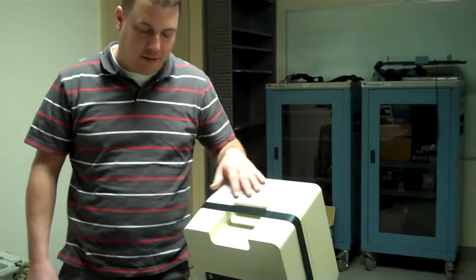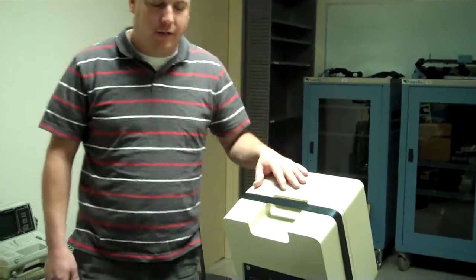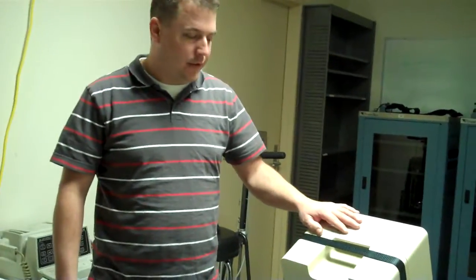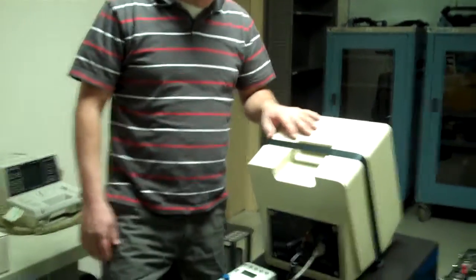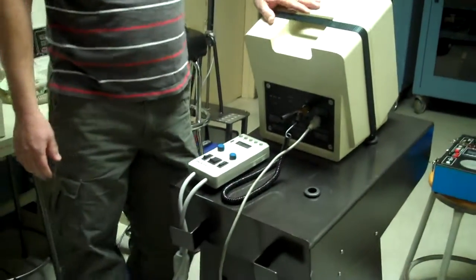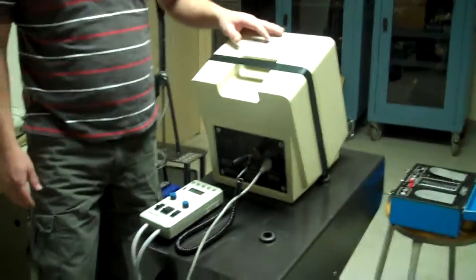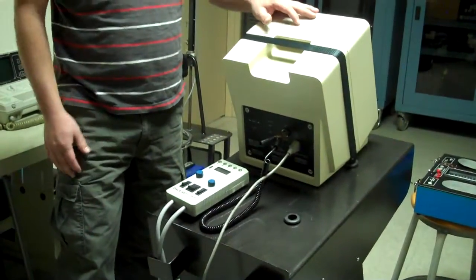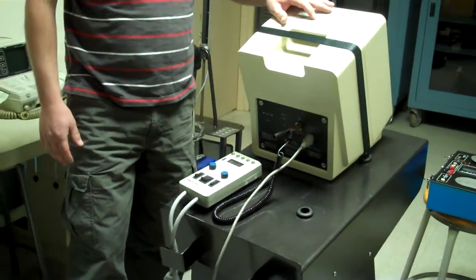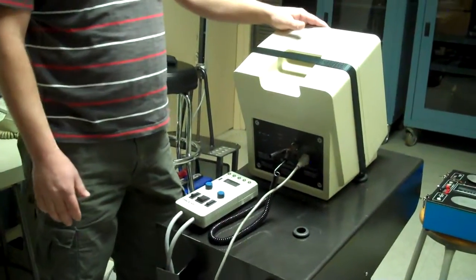Okay, continuing our PM on our LIFEPAK 9, we're going to do some quantitative measurements and complete our PM. So the first thing we're going to do is use the safety analyzer just to check some electrical values. We're going to check our line voltage, and we're going to check for leakage current, which is very important, especially in the hospital environment.